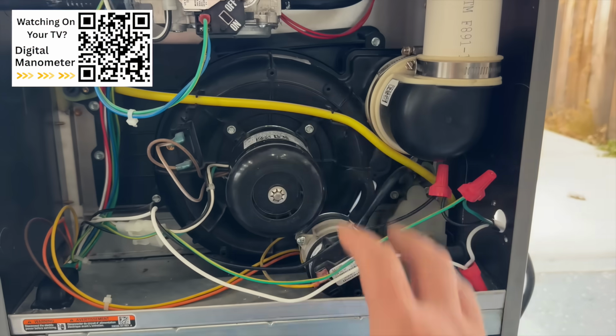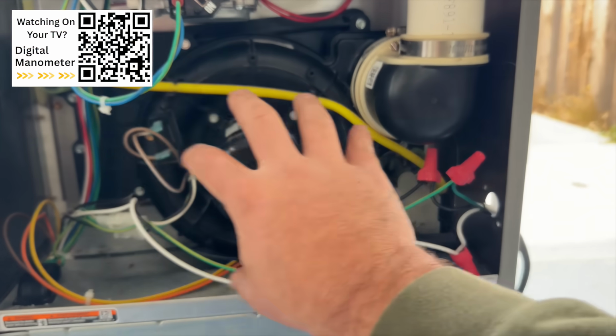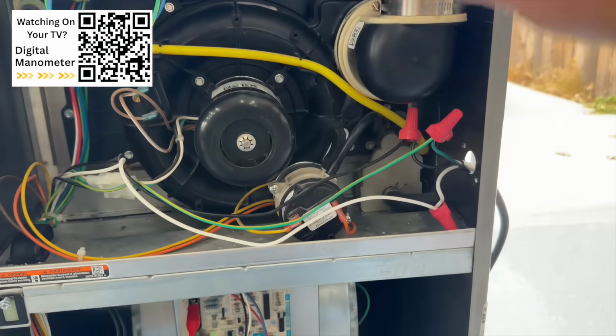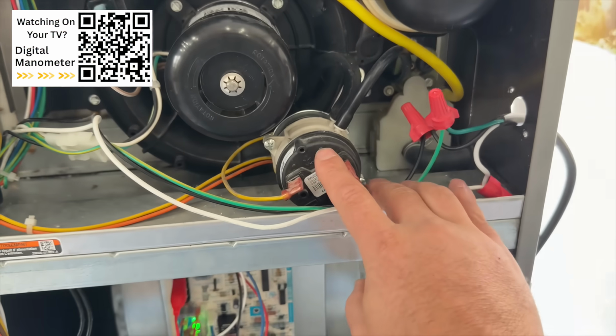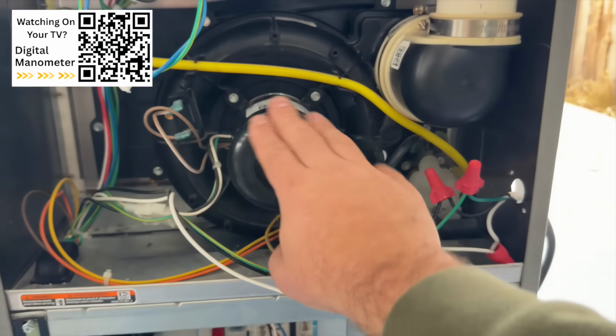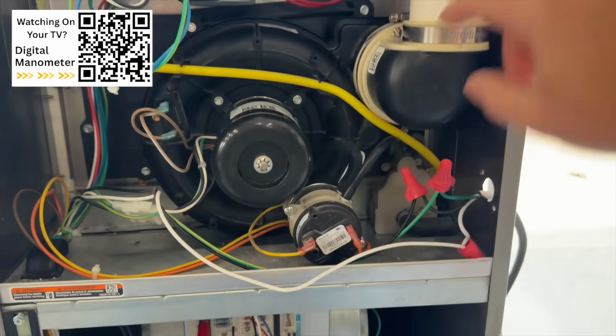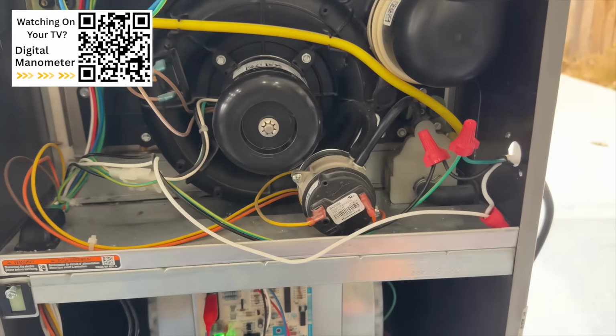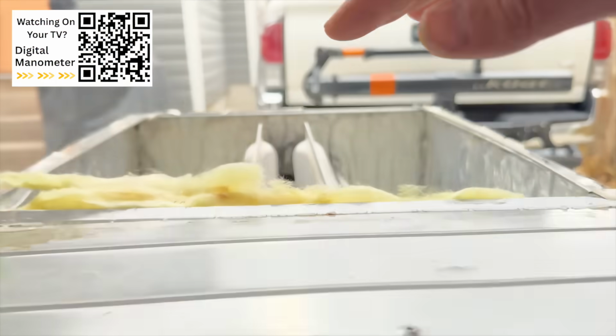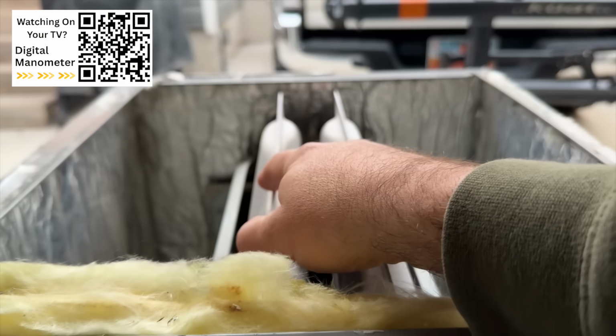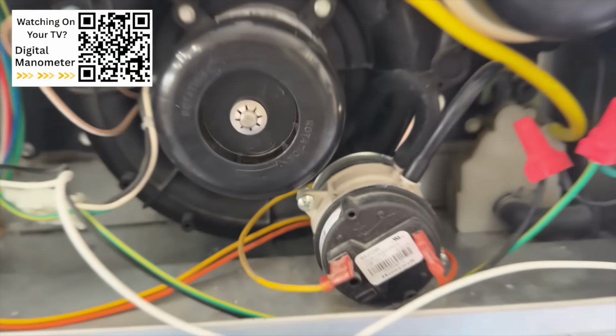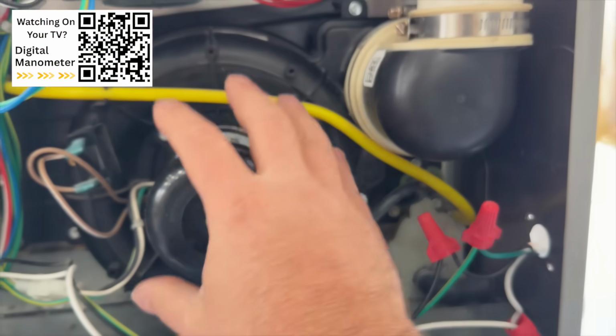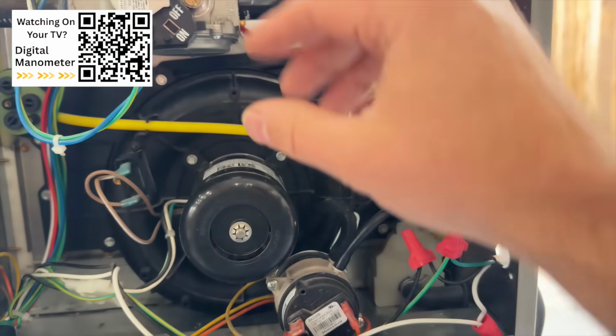And as we talked about before, the inducer, its job is to pull out fumes from here. And these are called pressure switches right here. And their job is to say, okay, this is pulling enough vacuum out that we can proceed with the combustion process. And as we discussed before, the air that's coming through here from the return that's blowing through your home is totally isolated from the heat exchanger. So this test involves hooking up our manometer to this side of the system, turning the blower on, and seeing if there's any pressure reading on our gauge.